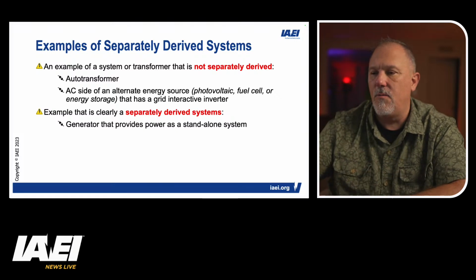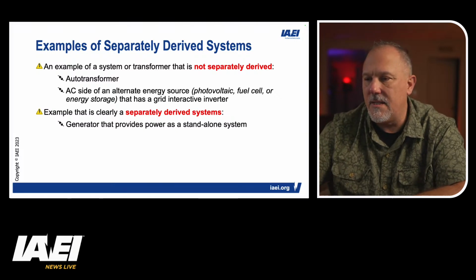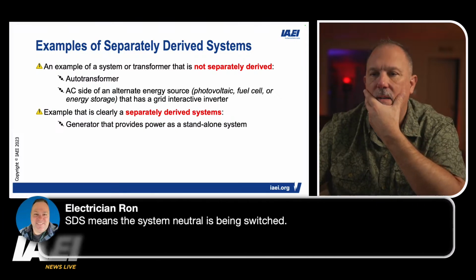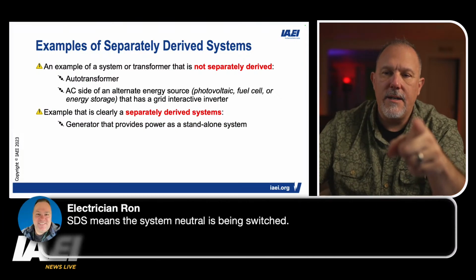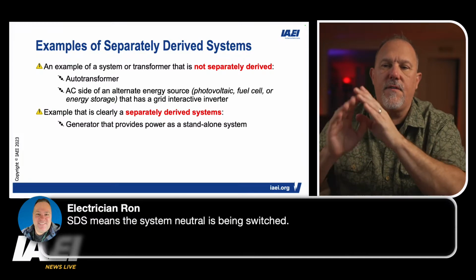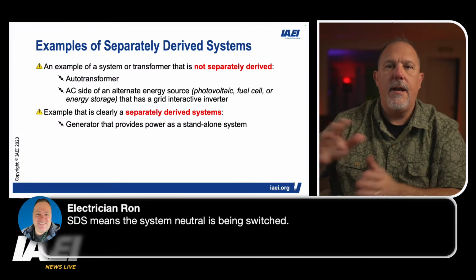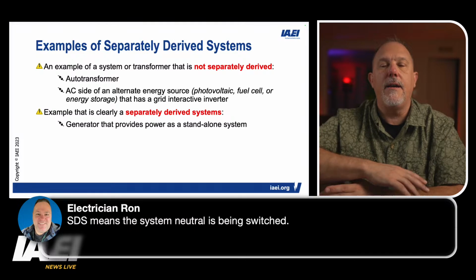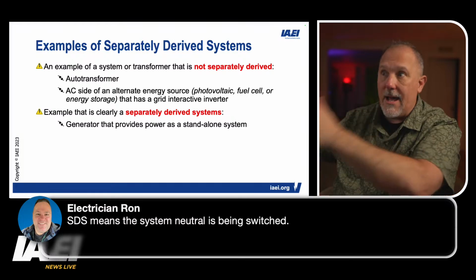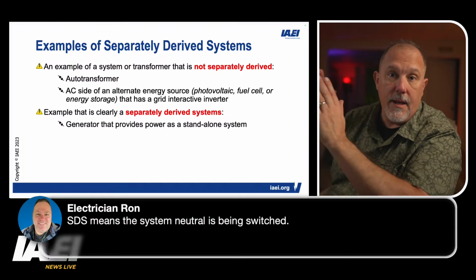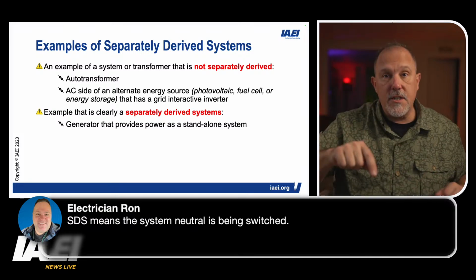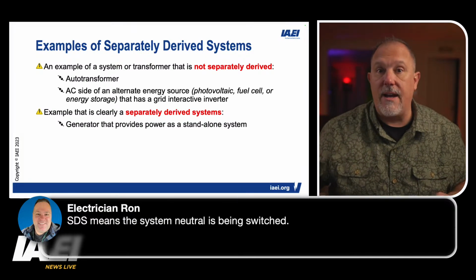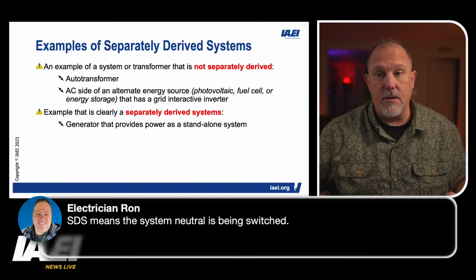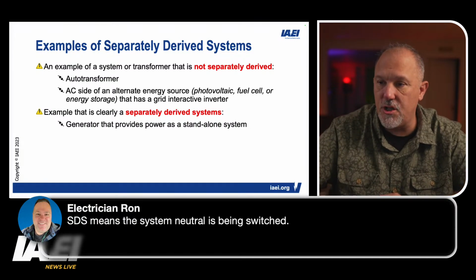My microphone was off. SDS means the system neutral is being switched. Yep, separately derived system. Now, if I have a generator application and I have that transfer switch, then I am switching that neutral. Now I have a separately derived system in that generator. If I don't switch that neutral, I don't have a separately derived system in that generator. So very good point, electrician Ron.